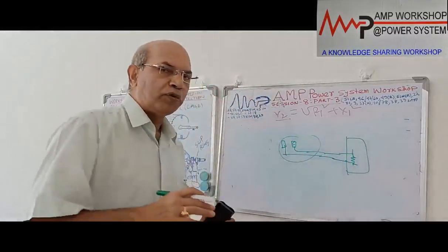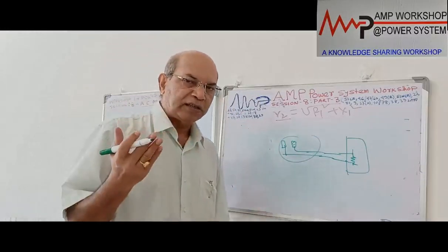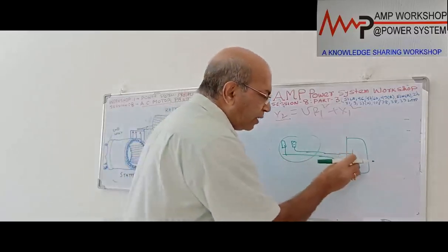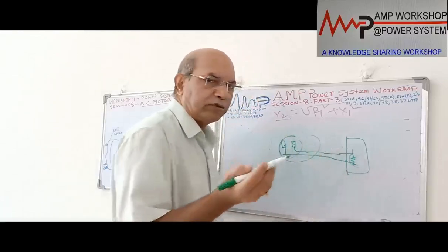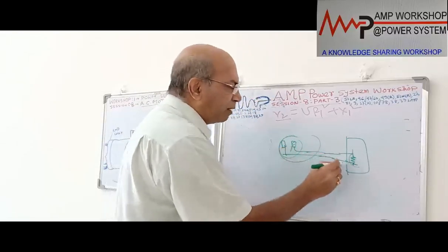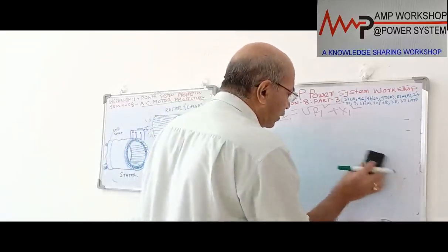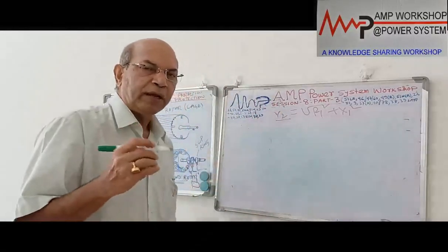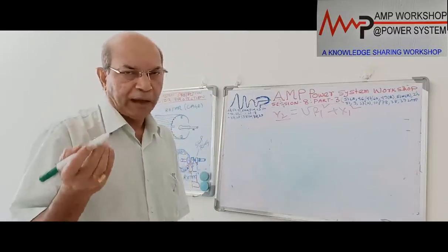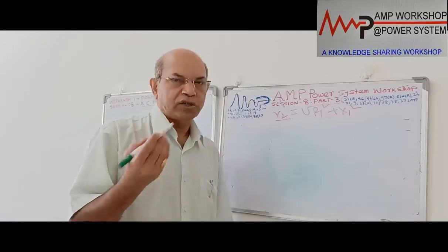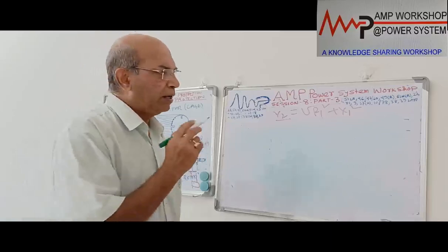This resistance value we feed to an RTD relay. That RTD relay is actually nothing but a Wheatstone bridge where three resistances are already included with the DC supply, and this resistance we add as the fourth. So in normal condition, when it is at ambient temperature, this resistance is balanced with the bridge. The moment the temperature goes up, the resistance value changes. Immediately the bridge gets unbalanced. Then there will be an unbalance current, which we already discussed. The unbalanced current is monitored, and if it goes above the set value, then correspondingly it will give an alarm or trip. That is the way this RTD works, and in that way we give the bearing protection.